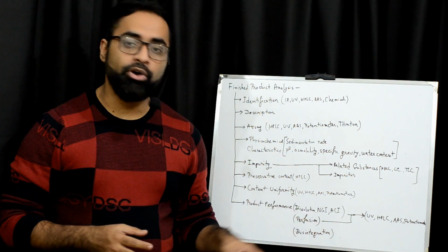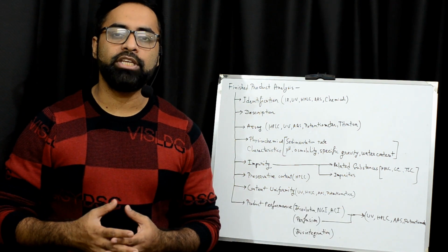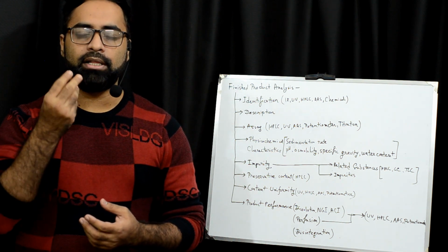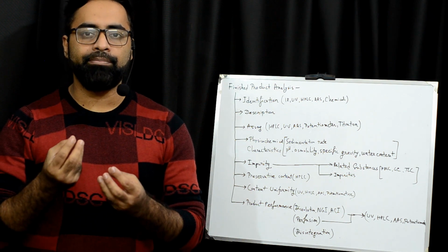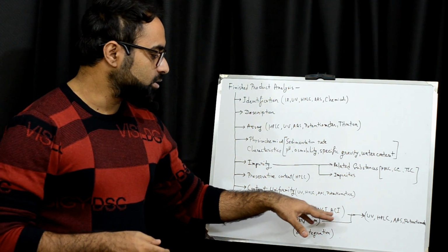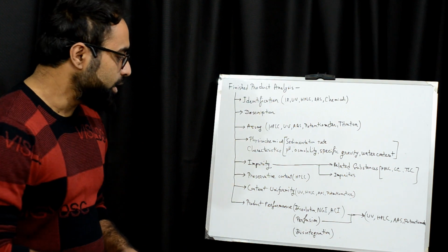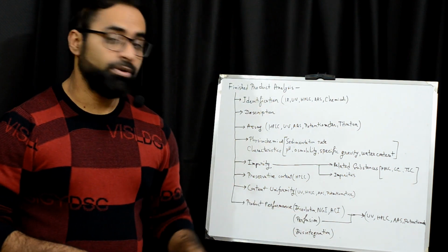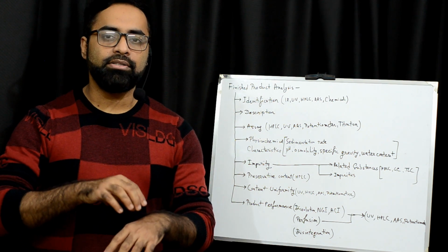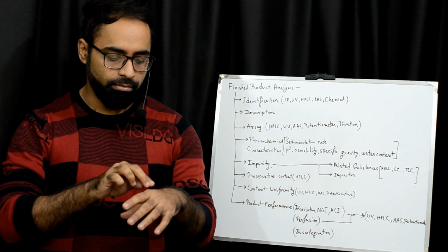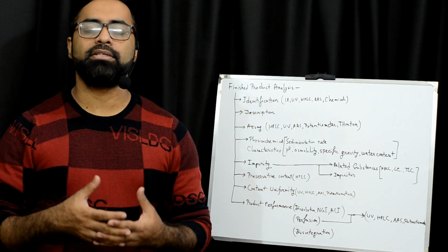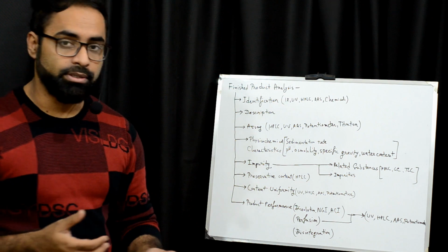Okay, there is also NGI or ACI. These sorts of impactors are used to check inhaler quality. Okay, if we take certain DPI or powder inhalers, are these being absorbed uniformly in the body, or is the particle size okay? We must check these through NGI, ACI or any other arrangements. And there is also perfusion, for example, if we test patches that are used on the skin, the drug must perfuse through the skin at the rate we have to ensure meets the acceptance criteria. This is also another product performance test.